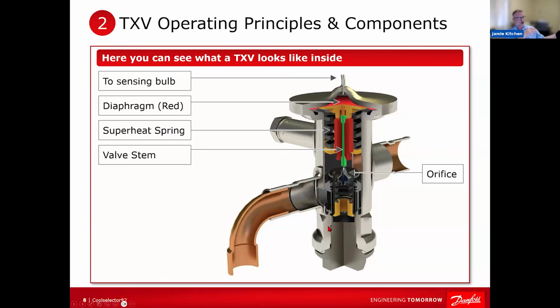So why didn't the filter dryer grab that stuff? Well, was the filter dryer 30 feet away and there's a whole bunch of braze marks on the line between it and the valve? I've seen it. Oh, yeah. Why not move that filter dryer closer to your expansion valve? It's not like it's going to break, or it needs to be kept a certain distance apart. And of course, if there's crap in the system on your TXV, there's probably more crap in the system that can let go too.